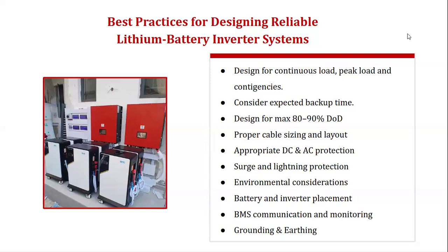I say very essential because you are dealing with lithium-ion batteries. They have communication ports and can pick up interference around them. If your system is not well screened, filtered, or shielded, the battery can pick up noise through the inverter and start misbehaving - it can shut down, or display a battery capacity that isn't real. Anything can happen. It's better to get it right the first time.